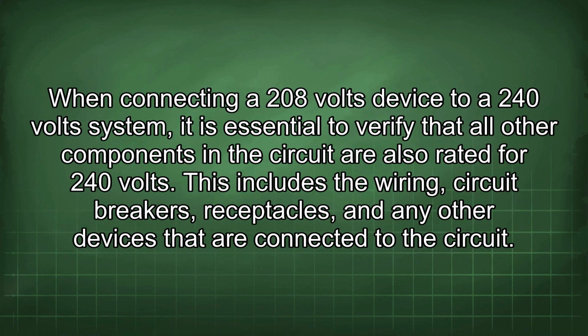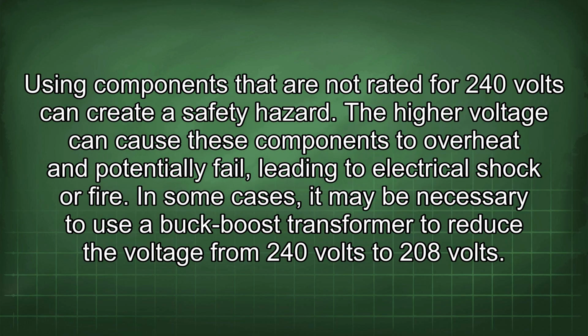When connecting a 208 volts device to a 240 volt system, it is essential to verify that all other components in the circuit are also rated for 240 volts. This includes the wiring, circuit breakers, receptacles, and any other devices that are connected to the circuit. Using components that are not rated for 240 volts can create a safety hazard. The higher voltage can cause these components to overheat and potentially fail, leading to electrical shock or fire.